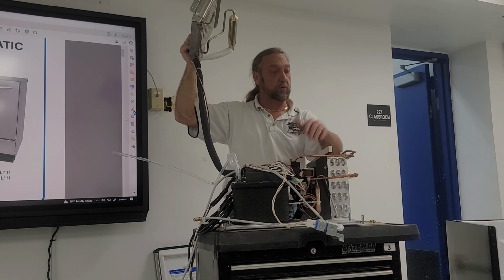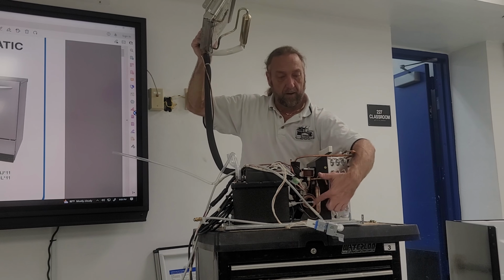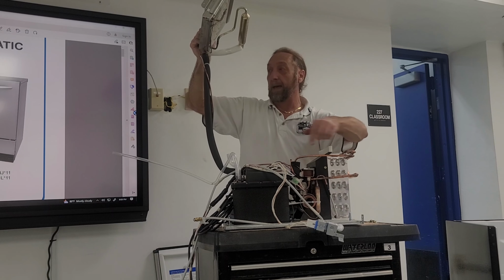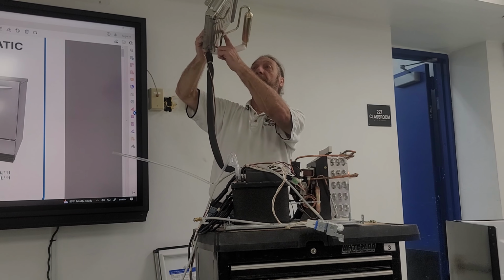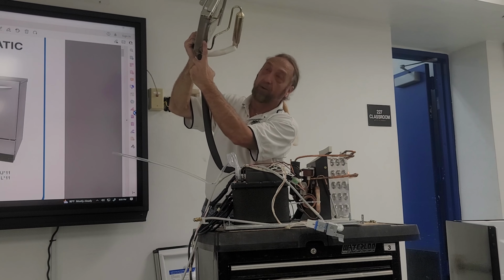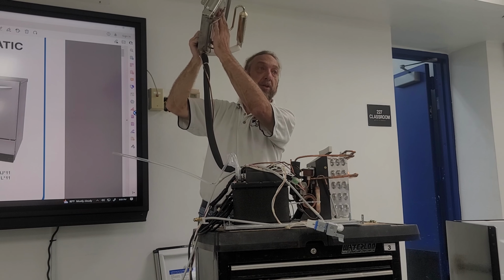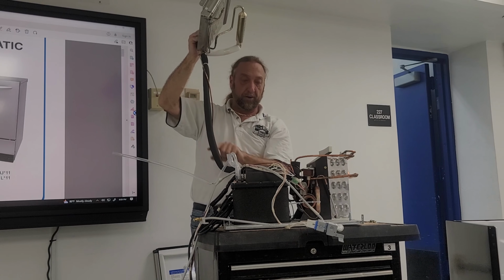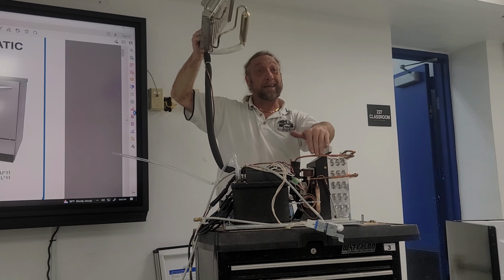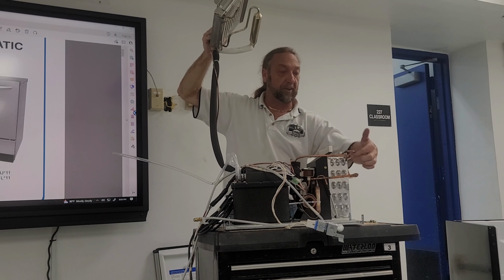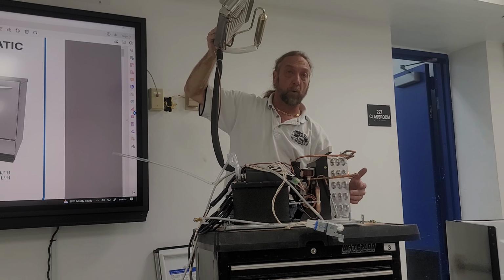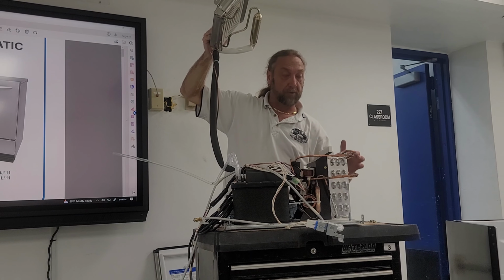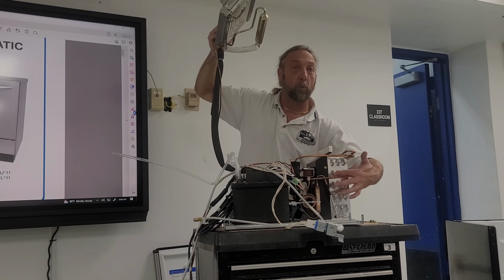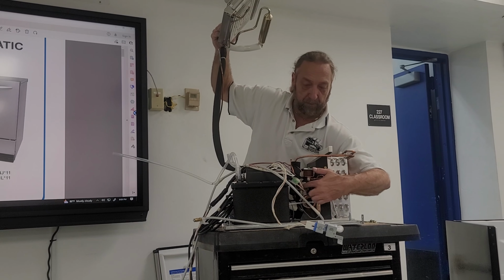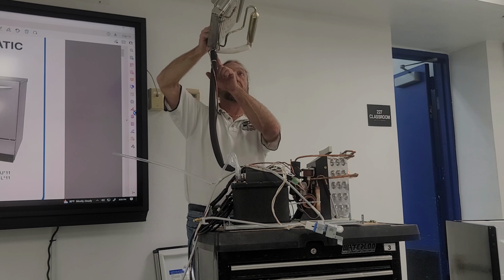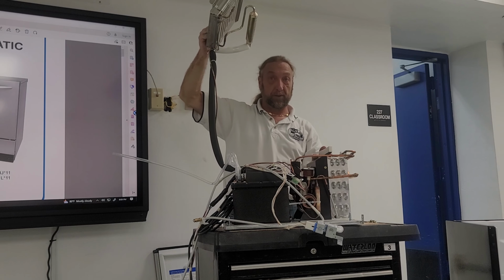When the hot gas valve is closed, the refrigerant runs through the condenser, goes through our filter and our capillary tube, and that capillary tube runs here up to the evaporator, and you can see it right here goes into the evaporator and goes into the evaporation here. Then it comes back here to our accumulator, back to our suction line and compressor. When the hot gas valve is energized, the compressor still pumps here into this tube. Some refrigerant will want to flow this way, but want to flow into the condenser, but the hot gas valve being open now causes the Freon to change direction. And then this piece here runs up to the evaporator and pumps directly into the evaporator without a capillary tube.